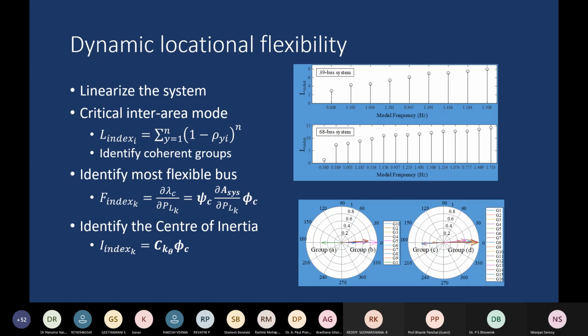So corresponding to such inter-area modes of oscillation, we identify the dynamic behavior of the generators, and we observe that the generators behave in groups. These groups are called coherent groups because the generators in a coherent group have very similar dynamic properties. Their oscillations are usually in phase, and you will have 2 or 3 groups oscillating against each other.